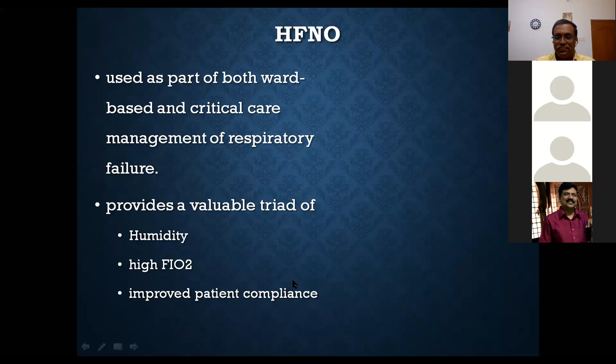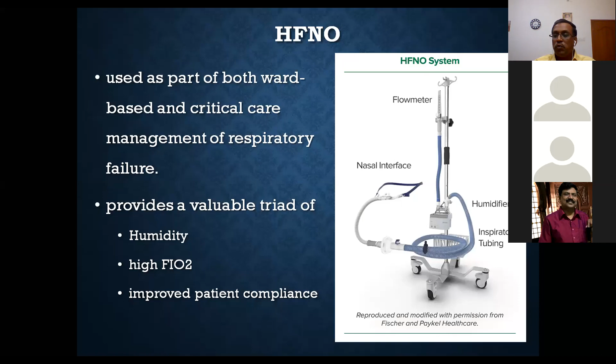It provides the valuable triad of humidity and very high FiO2. It is nearly 95 to 98%, even 100% FiO2 can be delivered to the patient, and it will improve the patient's compliance and comfort also. So this is the machine, the flow meter, nasal interface, and this is the humidifier. These are the inspiratory tubings, and this is the nasal interface. It's a wide bore nasal cannula that can deliver the highest flow rate of more than 50 liters per minute.